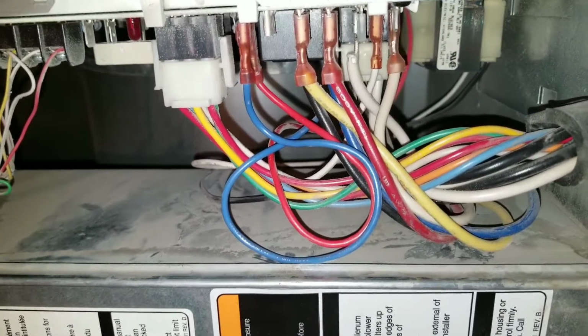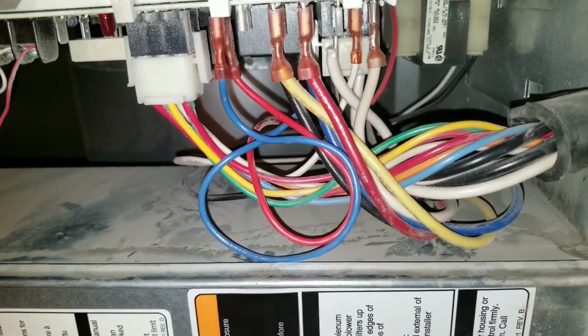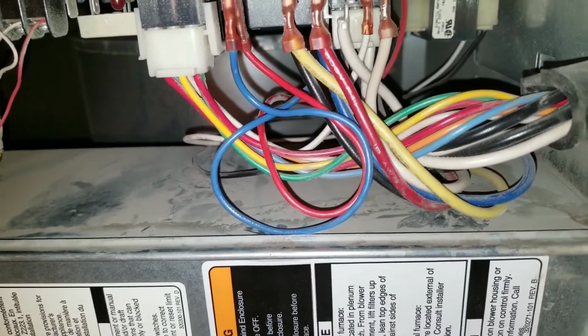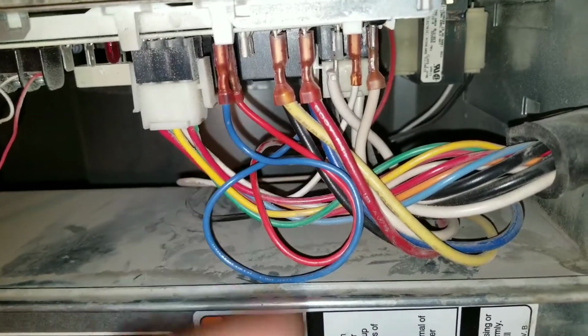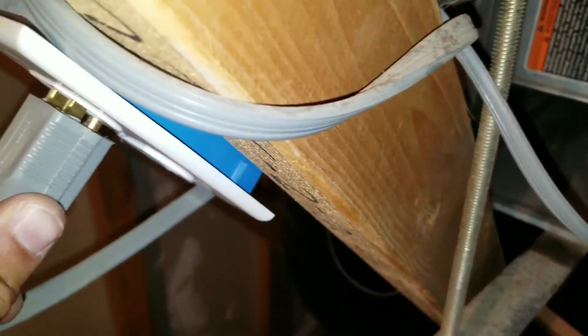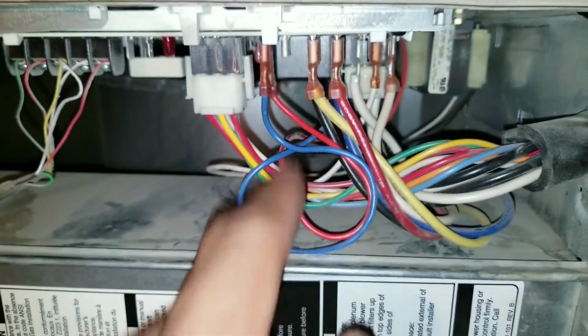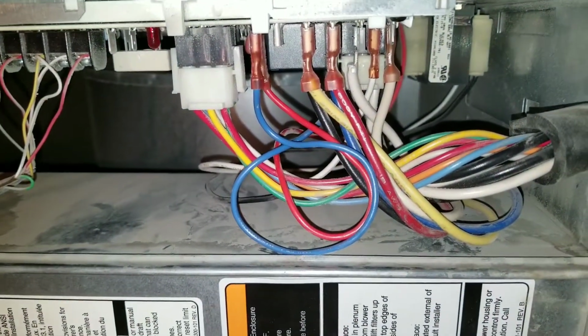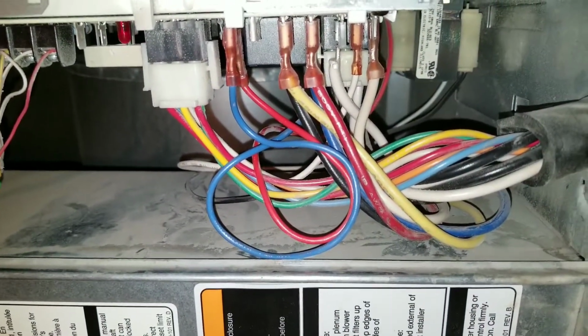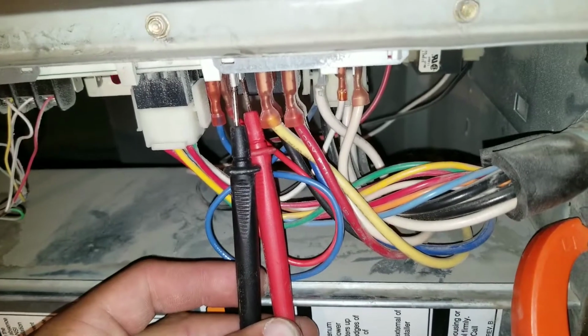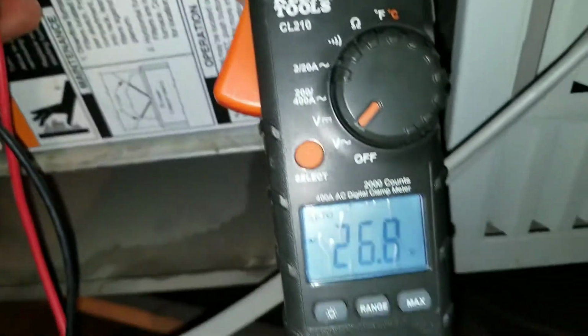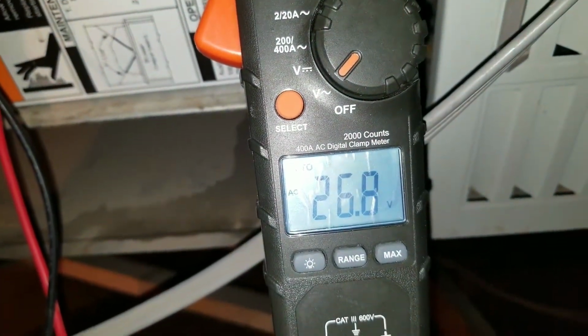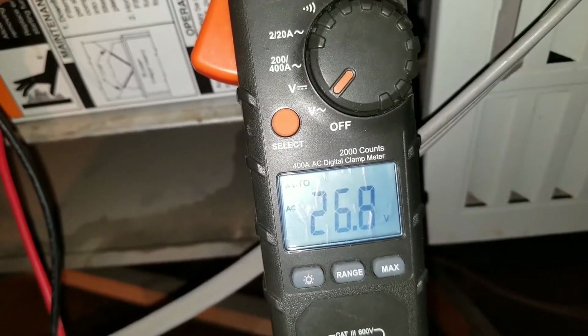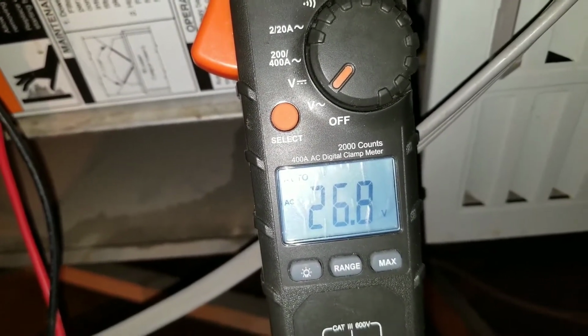Now remember, if you do not have your thermostat set to auto or cool or to heat, it's not going to get a proper reading. So we're going to plug it back in, and now I'm going to take my multimeter and I'm going to test these two probes. I'm trying to get a reading of 24 volts. Here I have my leads where my fuse was, and here is my voltage reading. I have 26.8. So anything between 24 and 28 should suffice.